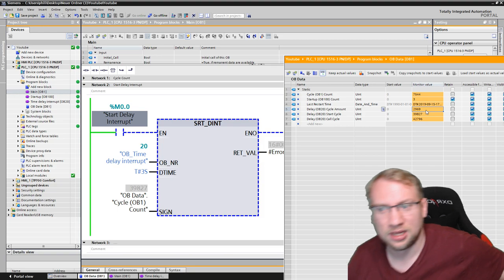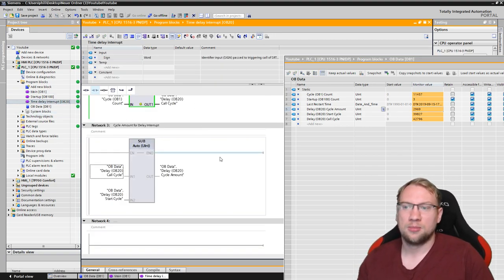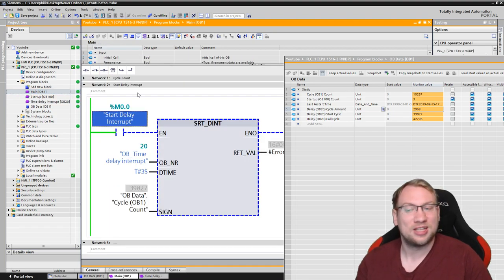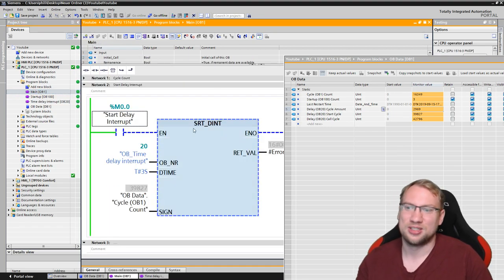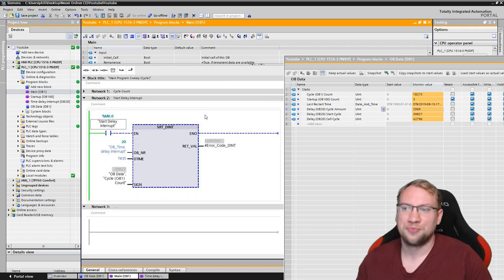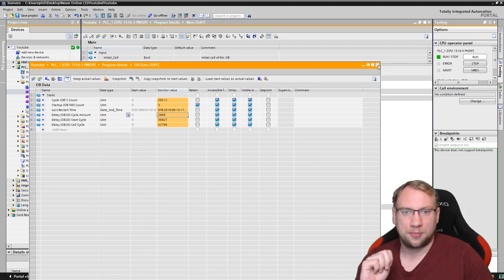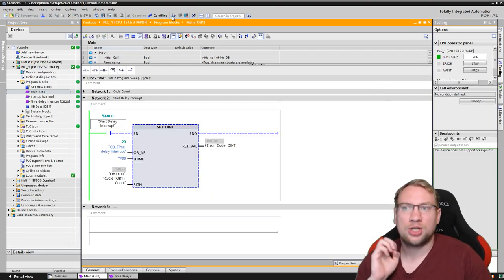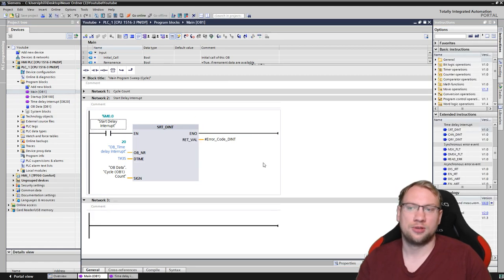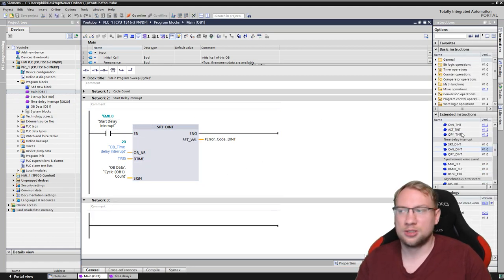So now I can actually evaluate how long has it been for my operating system of the PLC to execute this function. And I can see for three seconds, I have given it here three seconds, it actually takes 2,969 cycles. So not exactly one cycle per millisecond. You would expect maybe one cycle per millisecond, but it's not. It is varying a little bit. I can see that with this. I could put way more into the function here, but that's not what this video is about. It's just how can you use the delay interrupt.